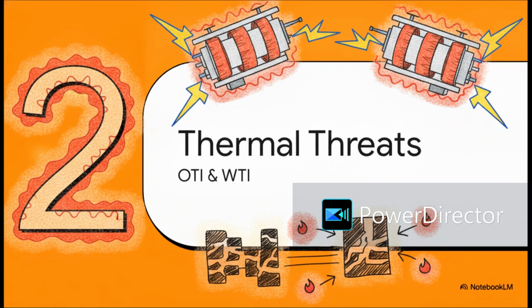Moving right along to Section 2, Thermal Threats, OTI and WTI. As a transformer takes on electrical load, it generates heat. And heat is the absolute ultimate enemy of its lifespan. If you let it run uncontrolled, it'll literally degrade the insulation right inside the unit. We monitor this using 2 main indicators, OTI for the oil and WTI for the winding.